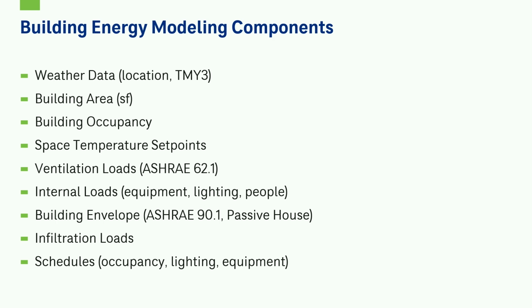Then we also have the building envelope, which helps mitigate the heat transfer between the ambient outdoor temperature and the indoor temperature of the space. The U-factor of the windows, walls, and roof can help reduce that heat transfer. There are code minimums through the International Building Code and also ASHRAE 90.1. And then there are more stringent and efficient standards, such as the Passive House design. Then we also have infiltration loads, which are when unconditioned air leakage comes into the building, which can affect your building load significantly. I already touched upon this a little bit, but it's really understanding your building schedules, when you're going to have people in the building and when your lights are going to be on, so you can understand when those internal loads are contributing to the heating and cooling loads.